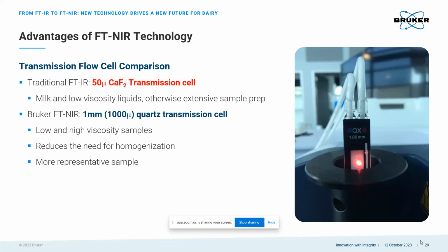And another important distinction is that most IR flow cells, again, use calcium fluoride as window material. And while these flow cells can handle milk and low viscosity liquids, other products are going to require more extensive sample preparation. And over time, these IR flow cells are going to be affected by cuvette wear. So this means the path length we just talked about is increased over time due to abrasive components and water in the sample. So what this does is it requires more monitoring and frequent adjustment by validation and standardization procedures. In essence, it's the reason why you'd have to frequently bias an IR instrument.